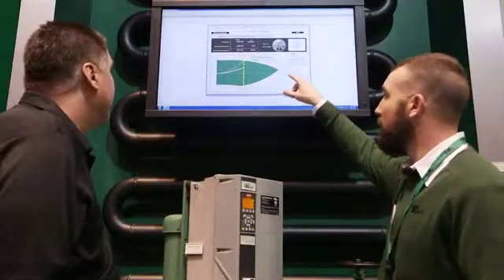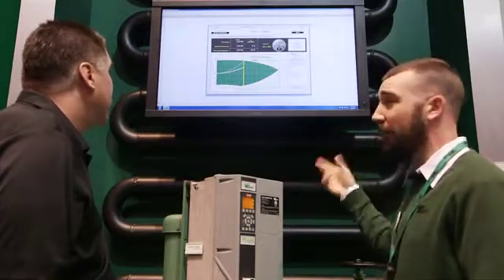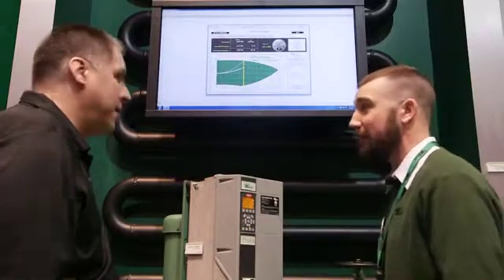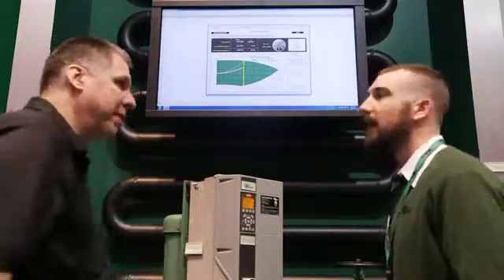If you look at the self-sensing Pro Balance, we'll see that we're at a 29% energy savings compared to if we were at the specified performance and cranking down on the MPV, we would have only been at a 6% energy savings. Substantial energy savings, especially in a big application where you might have multiple pumps. Exactly.